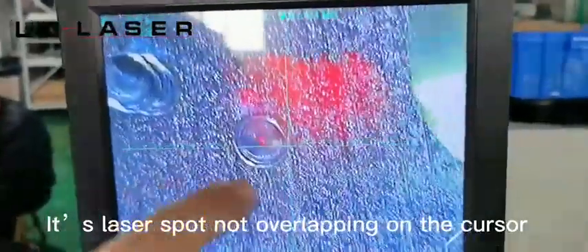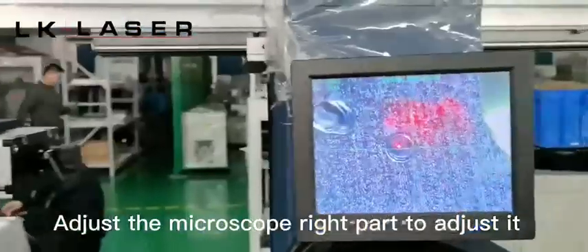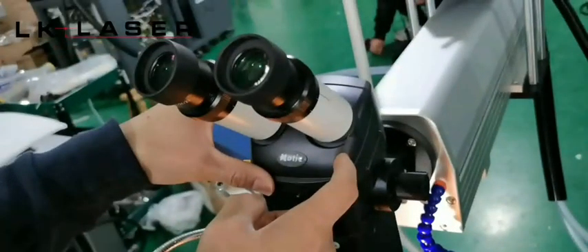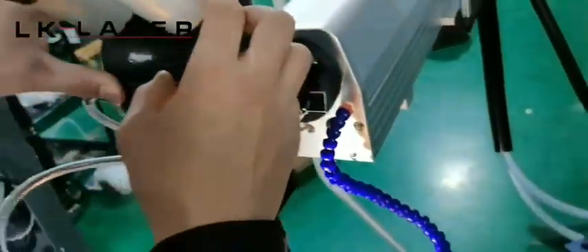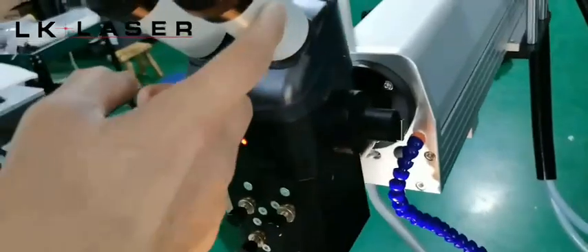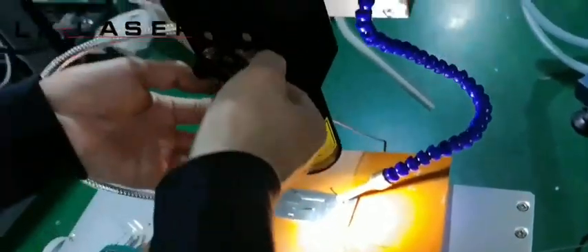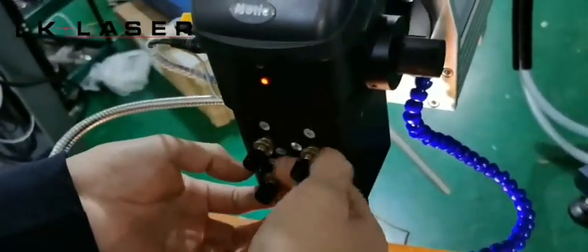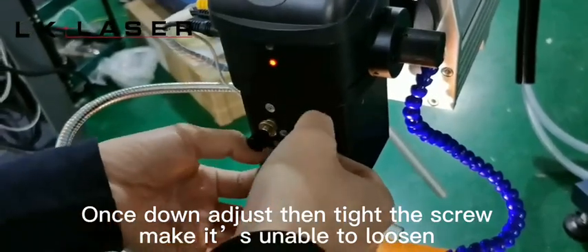And on the CCD display you could also observe the welding position. If the laser spot is not overlapping on the cursor, adjust the microscope right part to adjust it. Once done adjusting, tighten the screw. Make it unable to loosen.